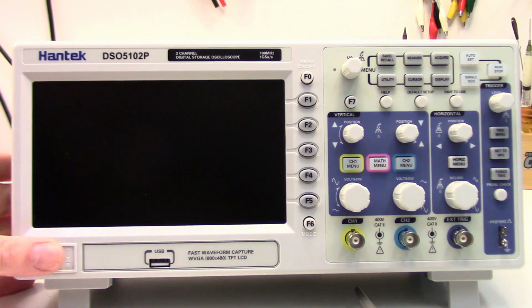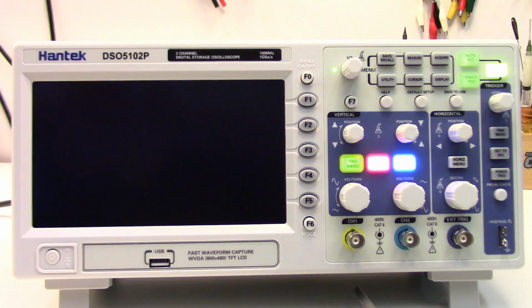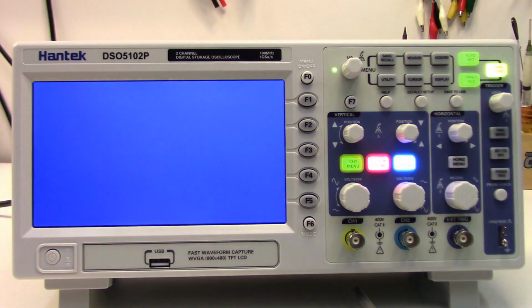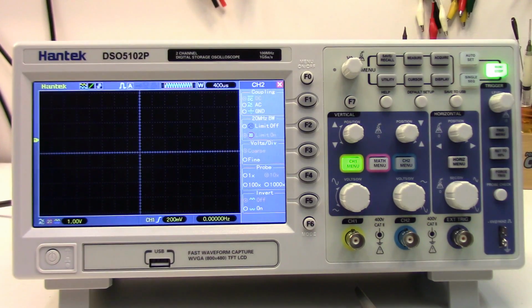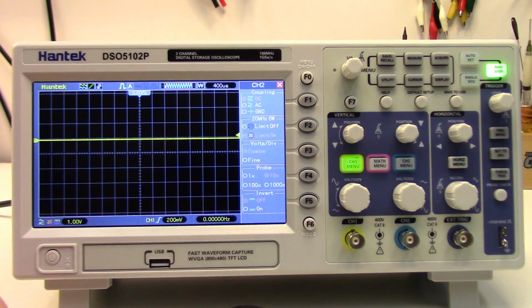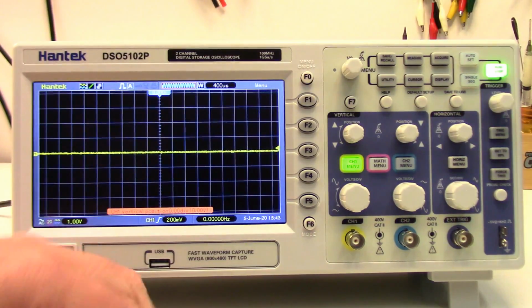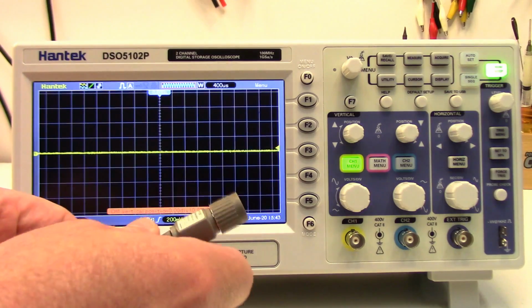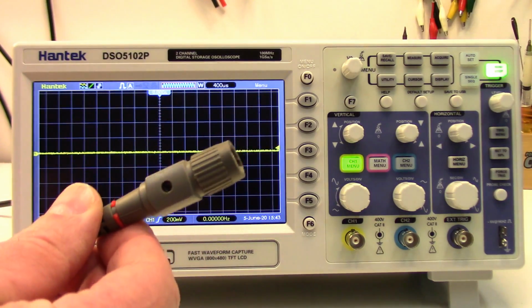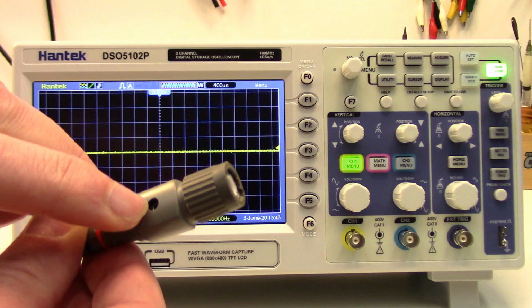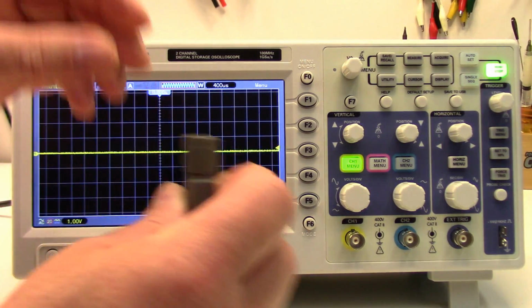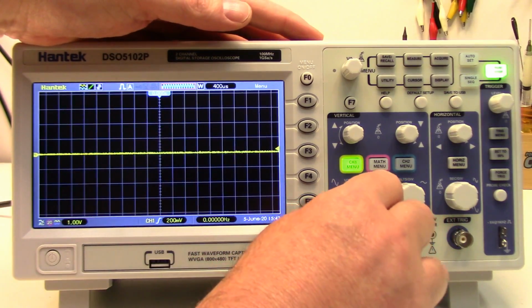Okay, I've got it plugged in. I'll power it up. See how long the boot time is. It's about 10 seconds. I've already timed it. And there we go. Just gonna turn this off. Reset that, and we will plug our probe in. So these probes have a little adjustment pot in them, which is basically a variable capacitor, and that's how you calibrate the probe.